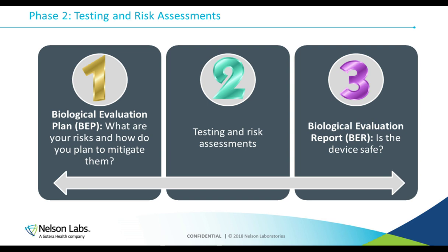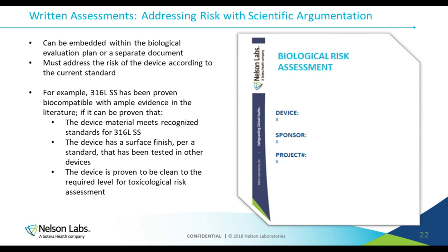Within this umbrella of part 2 of our 3-step process, we have the assessment and testing part. One of the things that can be really powerful when you're looking at the MDRs is the biological risk assessment. This is a document that's separate from the BEP and separate from something like a toxicological risk assessment. It evaluates certain risks based on all the information that's known about a device or a part outside of testing. This can be really useful, especially when materials are very common. For example, if it was the 316L part and we were saying we don't need to do sensitization on this, we'd say 316L stainless steel has been on the market for years, and give some data to support that.